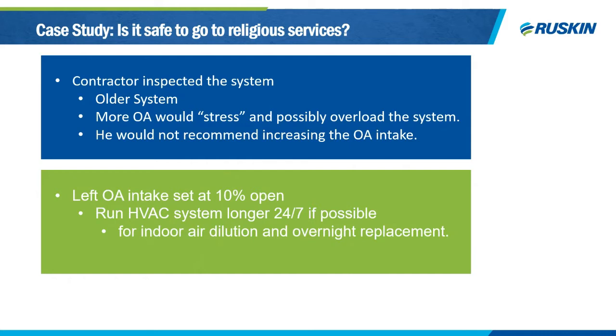The indoor air dilution and overnight replacement of the air in the building is what would be accomplished, so that you start off every day with new air in the building. If you left the damper closed overnight to save energy, then you would start every day with the air that was in there yesterday. So again, they're trying to displace the air that's in there.